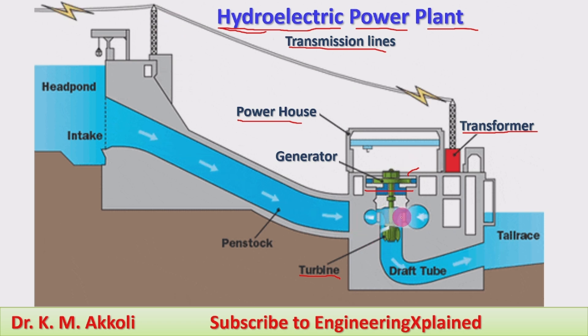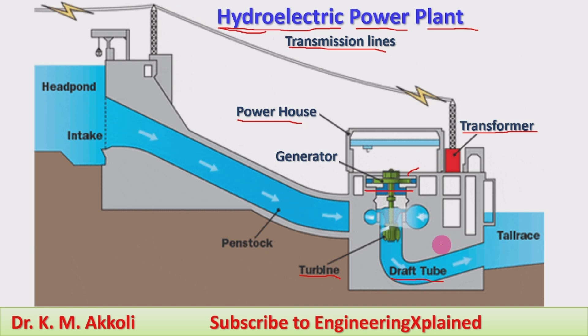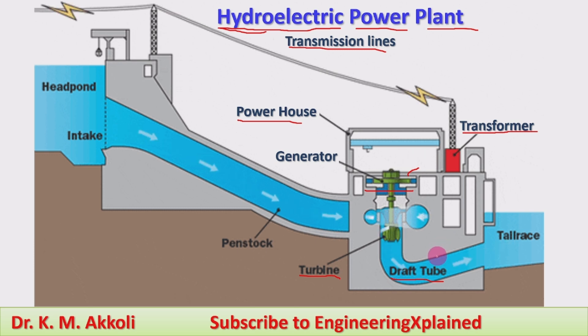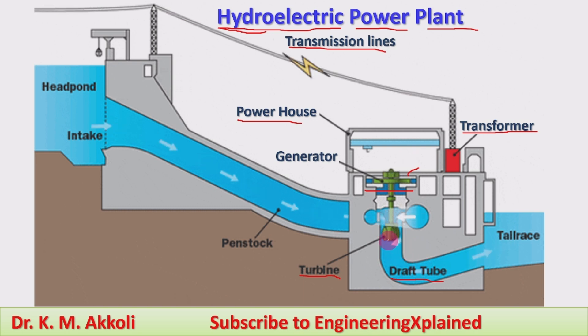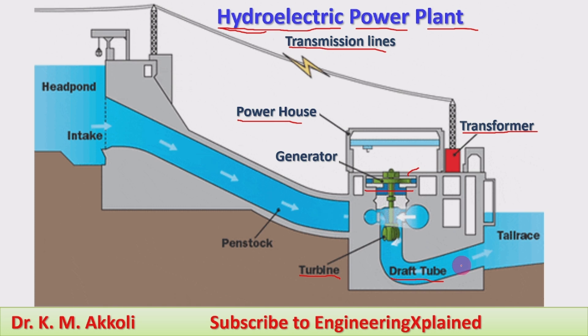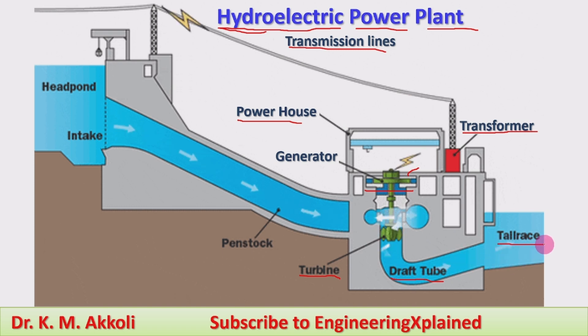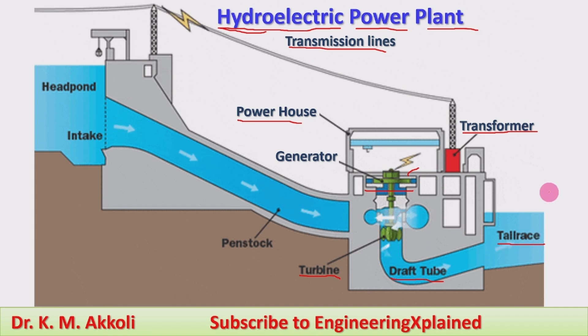After the water does its work, it is discharged through a draft tube. The draft tube has an increasing cross-sectional area, which increases pressure and reduces velocity. After converting kinetic energy into mechanical energy, the water's velocity reduces, and without the draft tube there could be back pressure. The draft tube prevents this back pressure, and the water is then discharged to the tailrace at a lower level.